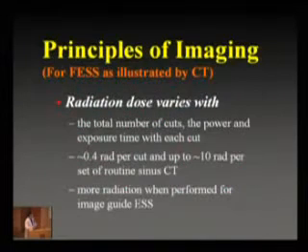But one thing is, the more cuts you have for the patient, the more irradiation the patient will have. And one of the rough calculations that we can refer to is, for every cut we have for the patient, approximately 0.6 rads of irradiation is received by the patient, referred to the lens, that is.